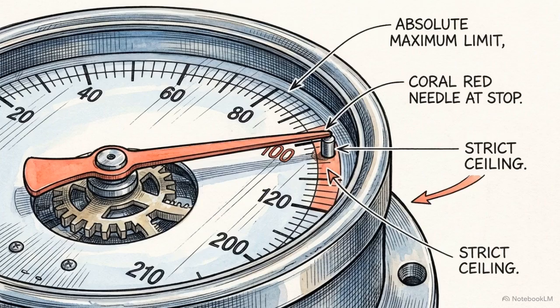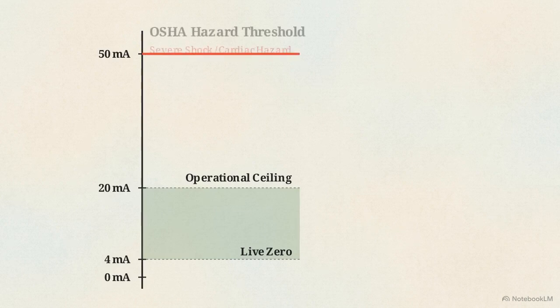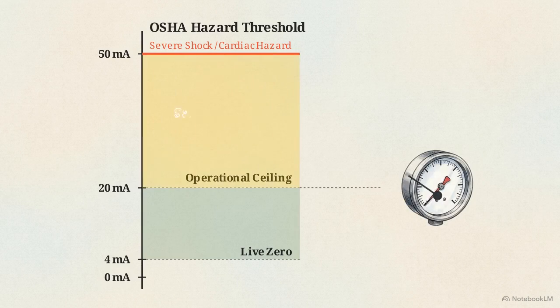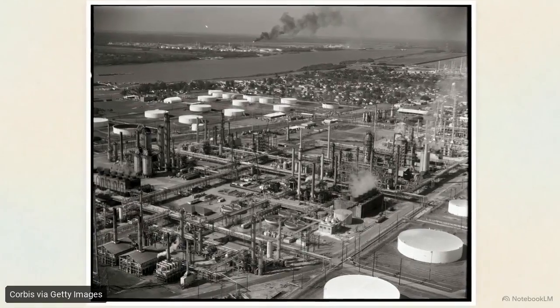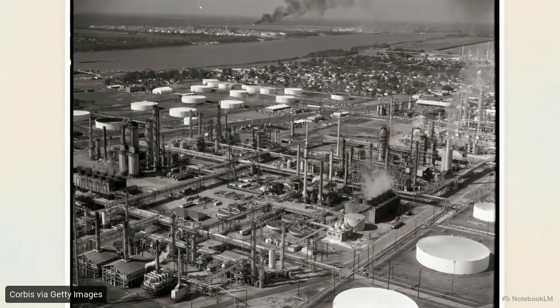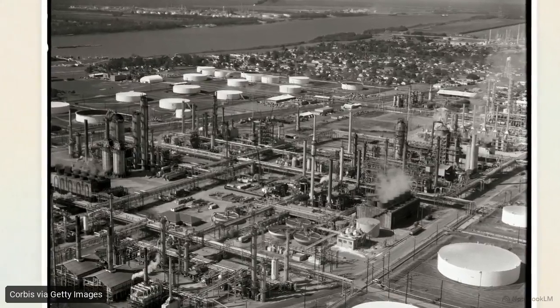But why establish the ceiling exactly at 20 milliamps rather than 30 or 50? This scale maps out the human safety factor. The Occupational Safety and Health Administration defines 50 milliamps as the threshold for severe shock and cardiac hazard. Capping the operational limit at 20 provides a strict safety margin for technicians working on live wires. It also enables intrinsic safety for hazardous environments, like chemical plants and oil refineries.